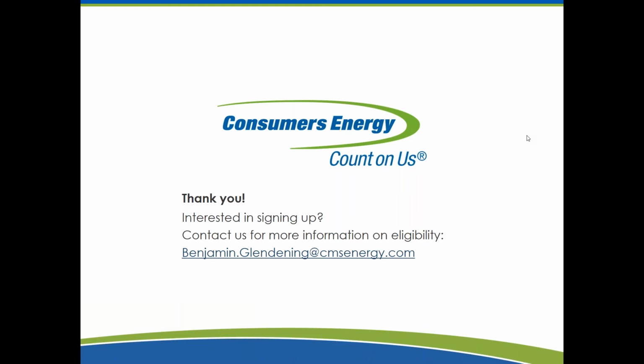And just to follow up, the percent savings, such as 30% for existing and 40 for new, is based on the building site, for total energy use, correct? Yes. Sorry, it's regulated energy use, right? So that excludes receptacle and process load. Okay, thank you for bringing that up. I think that was on the slides, but I probably brushed over it. Yeah, that's regulated energy use. So basically anything that's regulated by IECC and the ASHRAE 90.1 standard, which excludes receptacle and process load.